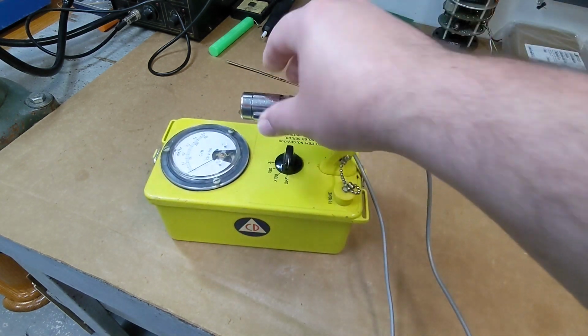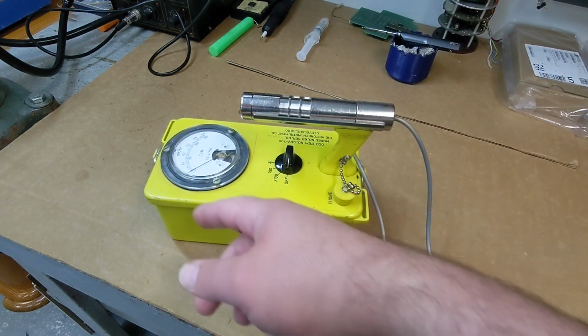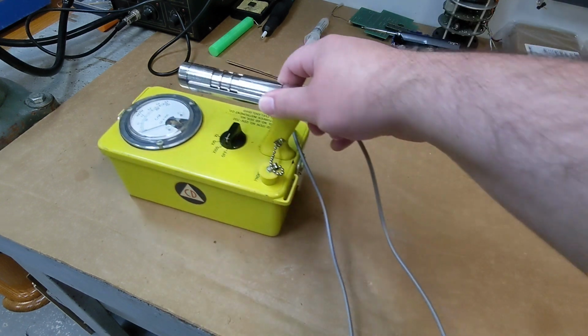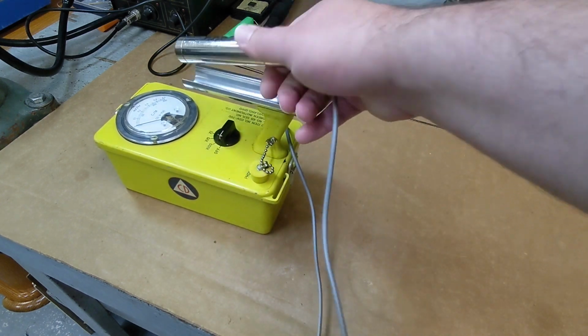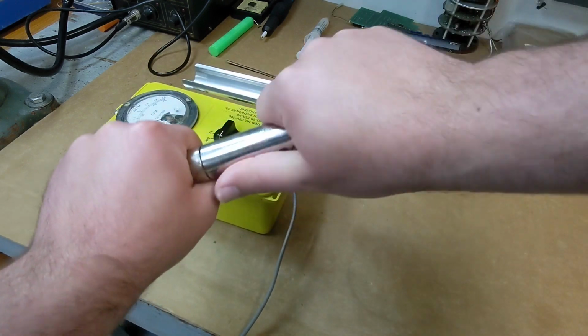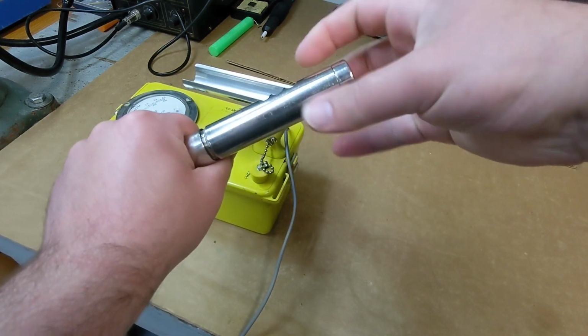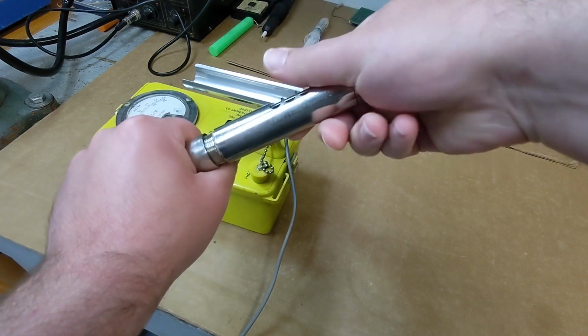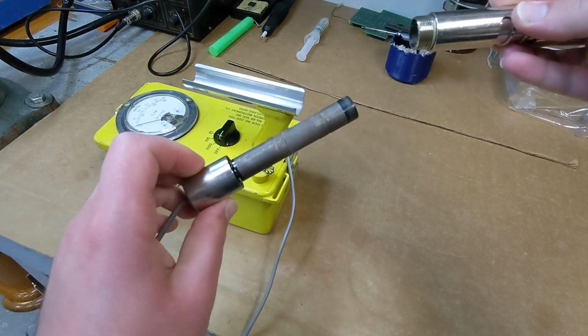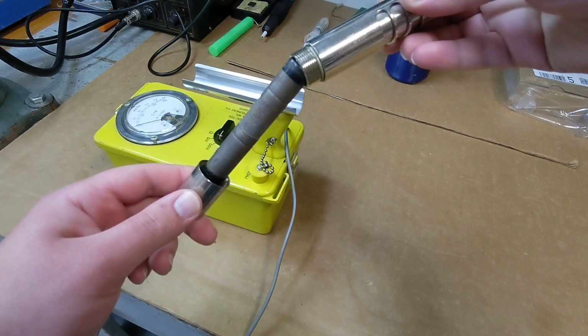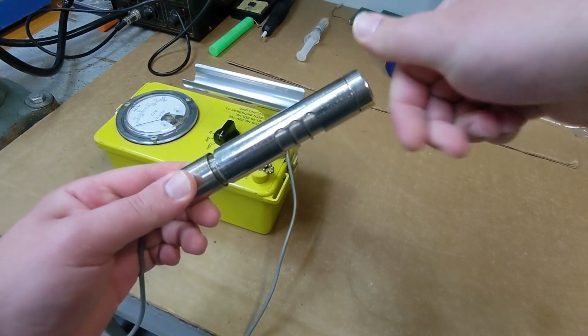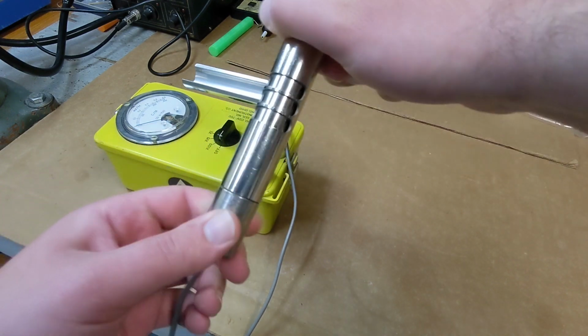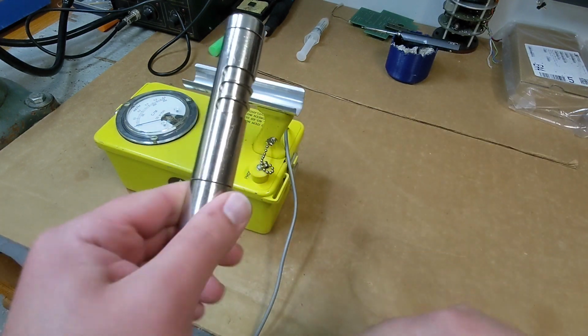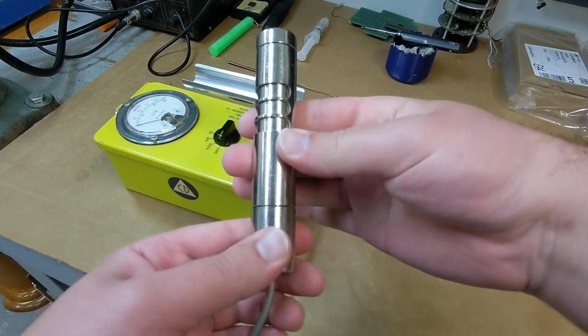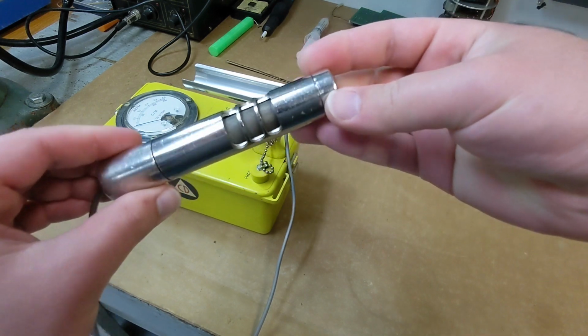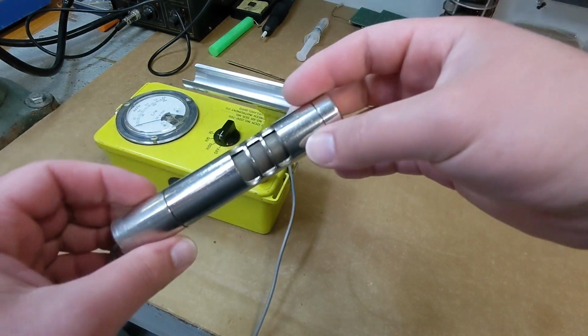There was the other model, the survey meter model, that's a much higher range, and then this is a Geiger counter model. And inside of here should be the Geiger tube on this little probe here. With the window closed, it measures gamma, and then if you open the window, it's also supposed to be able to measure beta.